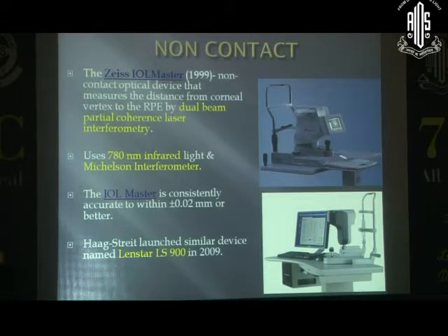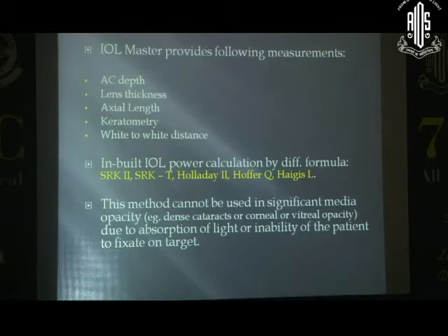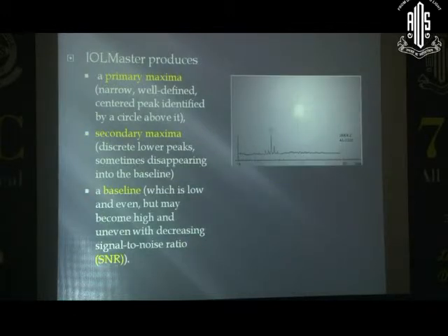Now you also have Haag-Streit, which launched LenStar in 2009. They provide anterior chamber depth, lens thickness, axial length measurement, keratometry and white to white in a single reading. Moreover, now you have all the new formulas in the machine, so you don't need to take the values to your internet and try to analyze them.